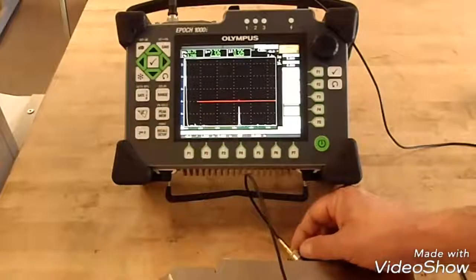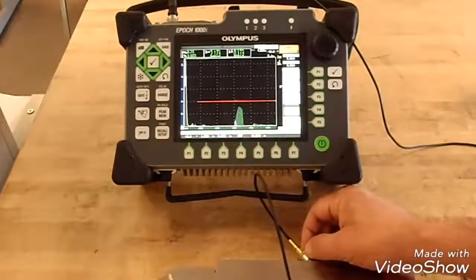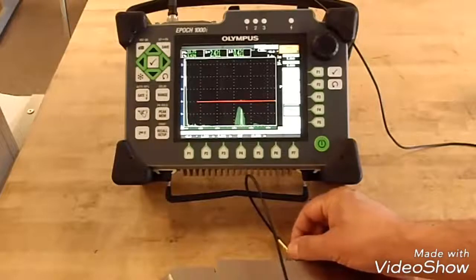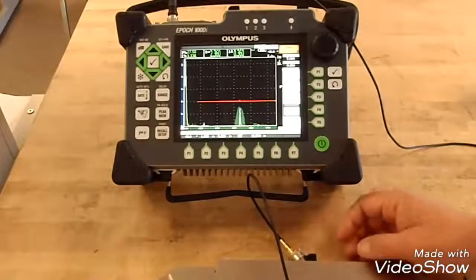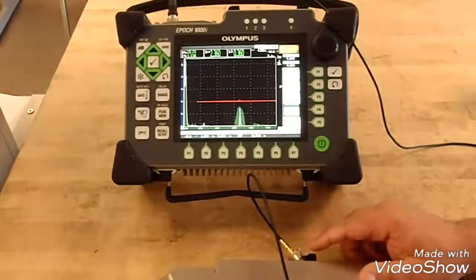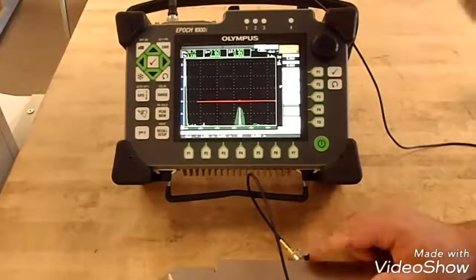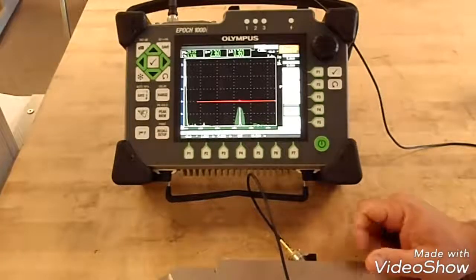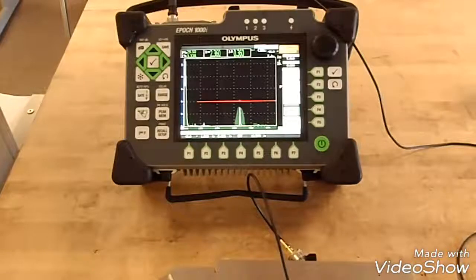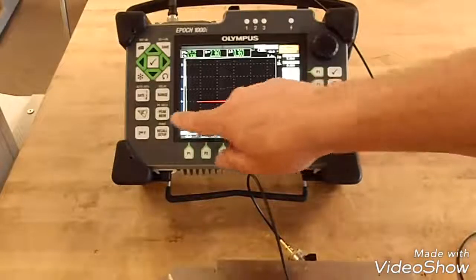In the direction of the large hole, peak your signal. Once your signal is peaked, look where the marking on your wedge lines up with the block. In this case it lines up at 45 degrees exactly, so now we're ready to calibrate.